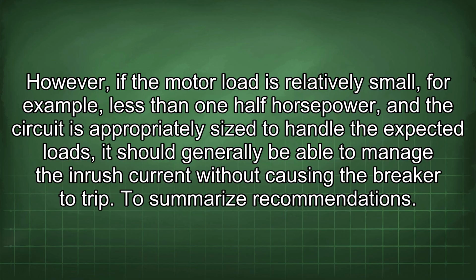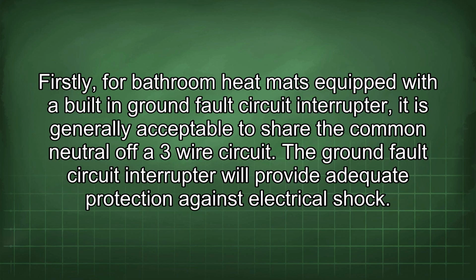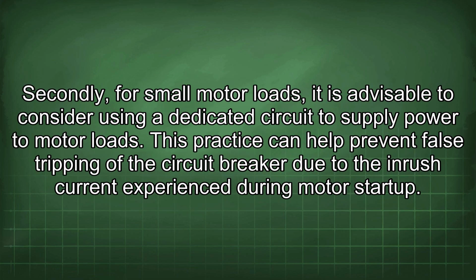To summarize recommendations. Firstly, for bathroom heat mats equipped with a built-in ground fault circuit interrupter, it is generally acceptable to share the common neutral off a 3-wire circuit. The ground fault circuit interrupter will provide adequate protection against electrical shock. Secondly, for small motor loads, it is advisable to consider using a dedicated circuit to supply power to motor loads. This practice can help prevent false tripping of the circuit breaker due to the inrush current experienced during motor startup.